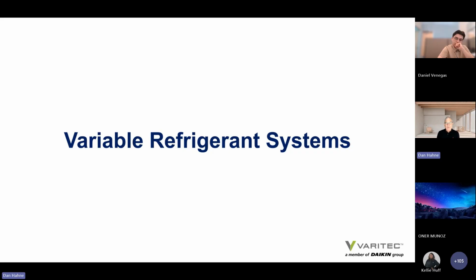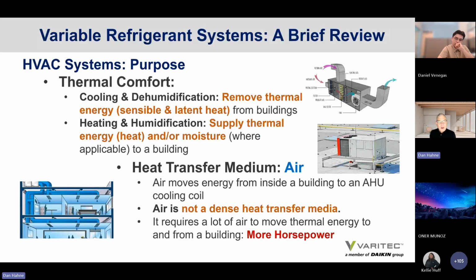So let's look at variable refrigerant systems. What are they? Well, remember, HVAC systems were fundamentally invented for thermal comfort in buildings. To create an environment that is comfortable, you have to remove thermal energy. And thermal energy is comprised of two types of heat loads: the sensible heat load, which is actually measured at a thermostat and is felt on the skin as heat, and latent heat, which is the amount of heat energy necessary to keep water in a vapor state. HVAC systems provide the cooling and dehumidification of buildings to maintain thermal comfort by maintaining space set points.